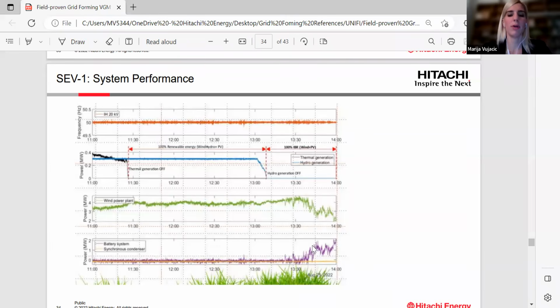Also in this case, the power store operates always as grid forming, and you can see here that at the moment when both thermal generators and hydro power were off, how the battery energy storage system supports frequency control in case of unstable wind generation. As you can see here, there is actually no contribution from the synchronous condenser to keep frequency stable around nominal frequency, in this case 50 Hertz.